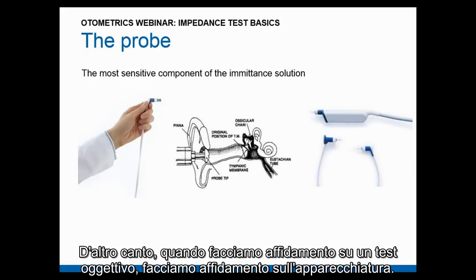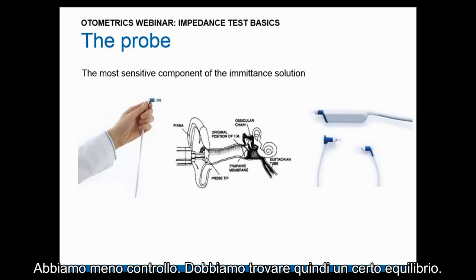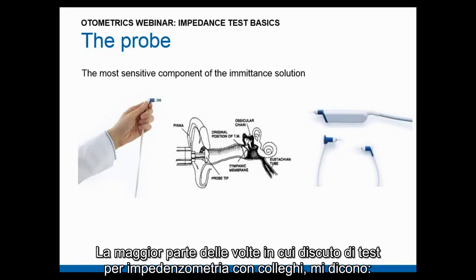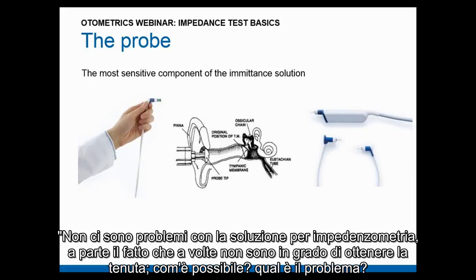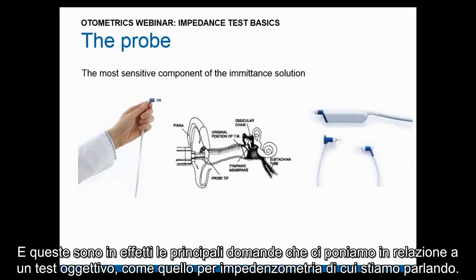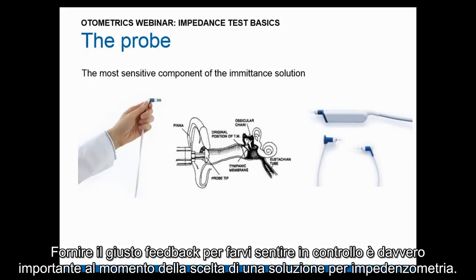On the other hand, when relying on an objective test, we rely on the machine and have less control. We need to find a balance. Most professionals tell me they have no problem with the immittance solution, except that sometimes they can't achieve a seal. The question then is: is it me, is it the patient's ear, is it the solution, or is the device not working properly? Providing the right feedback so you feel in control is very important when selecting an immittance solution.